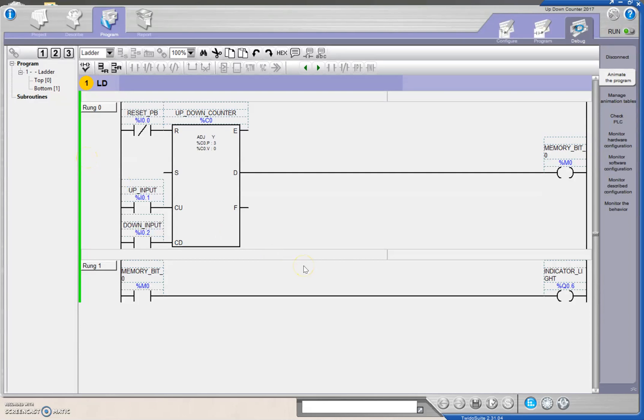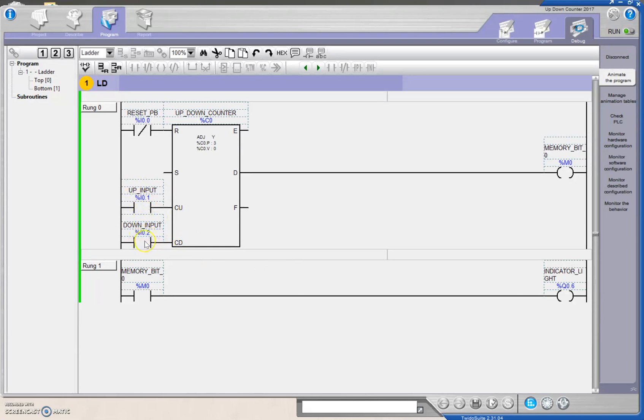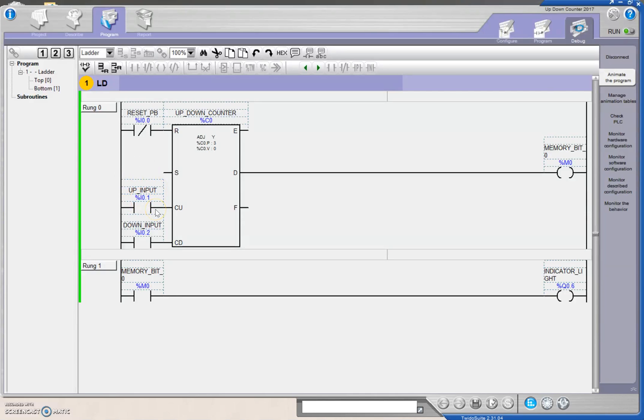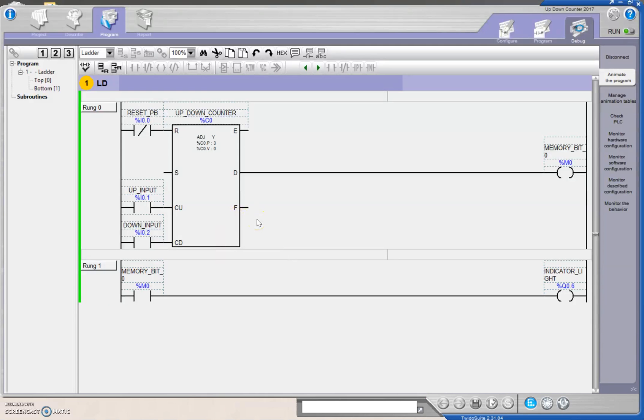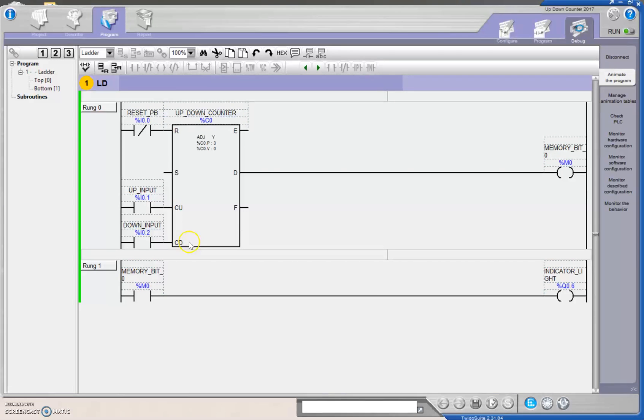So we have now created an up-down counter. A countdown counter literally just has an input here and we would eliminate this guy here for the countdown. Now, on the Allen Bradley, you have to use two counters and address them the same for an up-down counter. The beauty of this TwidoSuite is that both of them are in the same instruction here. You just have to provide it with a different input.